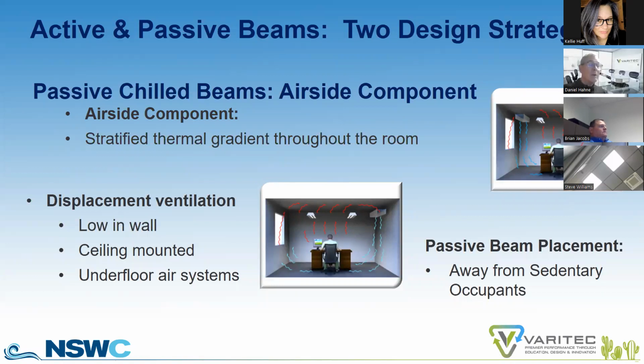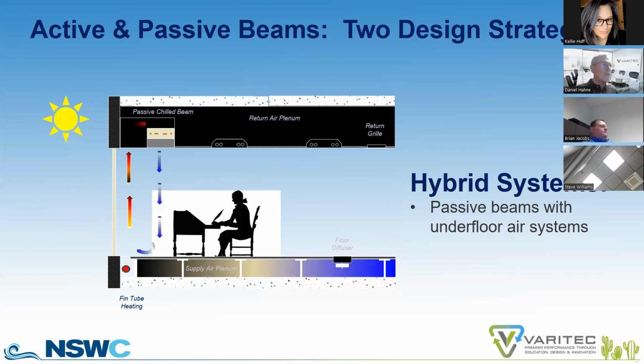I didn't hear of this 10 years ago, but we are now able to lay out underfloor systems with UFAD plenum heights of 10 inches, maybe as low as 8 inches in height. So we don't need 16 inches of plenum height for an underfloor system in order to provide perimeter cooling on a building. And that's a whole other concept to discuss. So displacement ventilation is the air delivery solution of choice to create a thermally stratified environment.